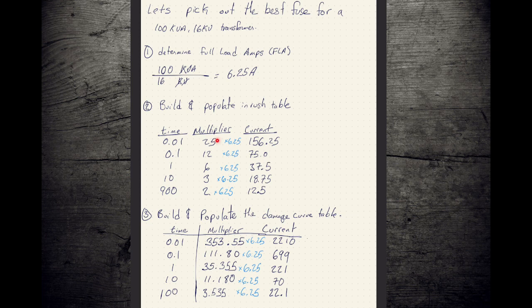So you build your inrush table and you multiply everything by your full load amps, and out comes your inrush currents expressed as amps. And then we're going to build our transformer damage line. So we have our times. Again, keep a note, 900, 100, not the same. We plug those times into our formula because the IEEE is full of engineers and scientists and they love formulas, and we end up with our multipliers. We multiply by our full load amps, and out pops our damage current thresholds for each of those times.